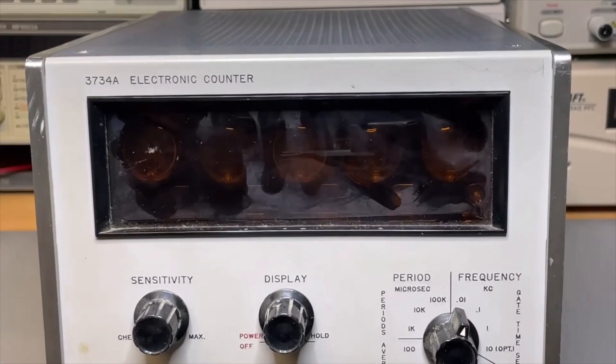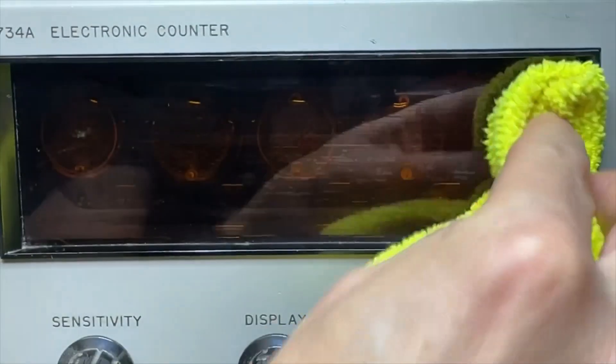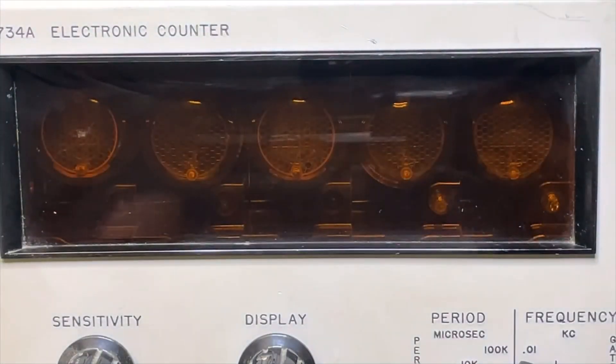I got a little list with serial numbers but I didn't see where my serial number fits in there, so for me it's a surprise if it's 2, 2.5, or 5 MHz. We already had a brief look but I'd like to zoom in a little bit more. We can see it is a 5-digit Nixie. Let me clean because I think, and this is my first meter that has this, we are looking at the top of the Nixie instead of the side.